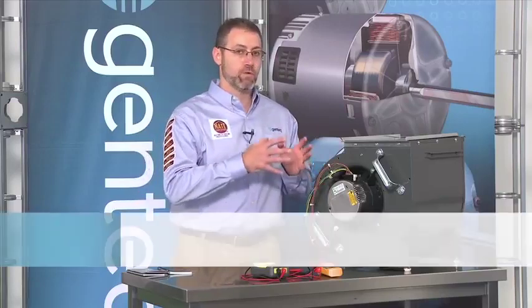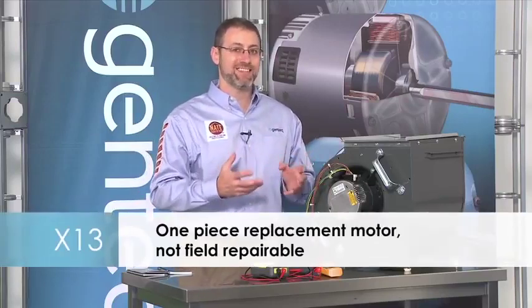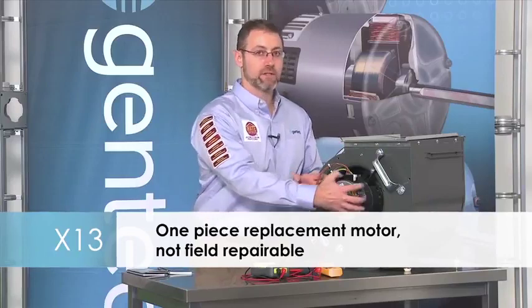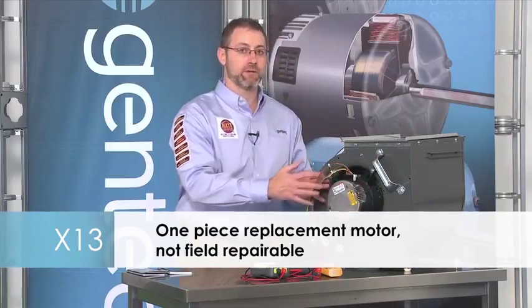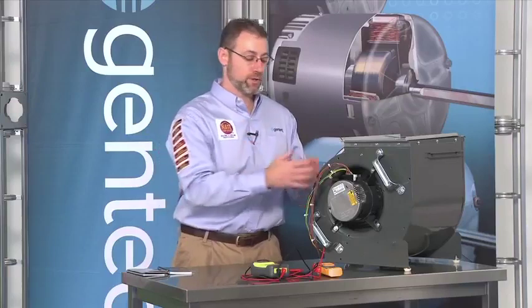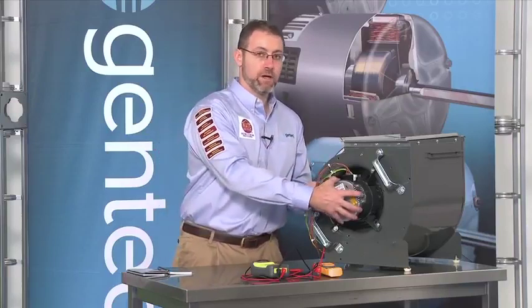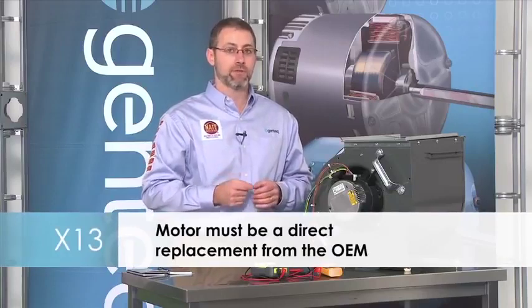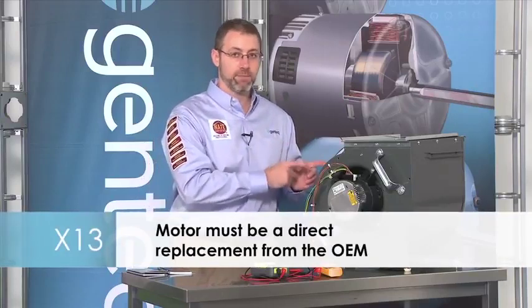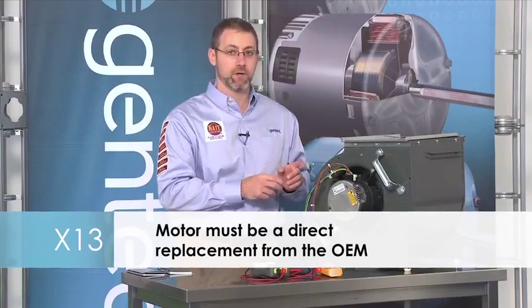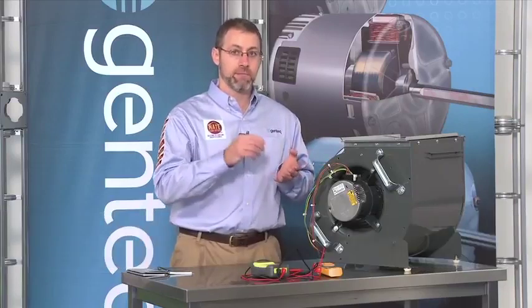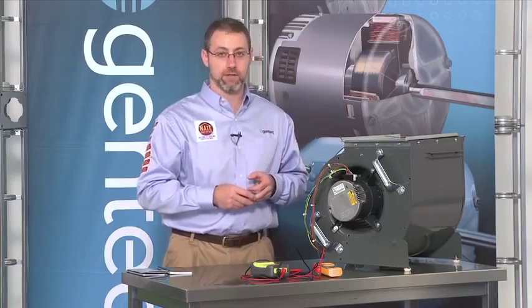If the X13 motor needs to be replaced, keep in mind that the X13, unlike variable speed, is a one-piece motor. Even though it is an ECM motor, it does have a control inside this motor shell. The X13 can only be replaced as one part. So if the motor's failed, you will get one whole motor and control assembly from the manufacturer. And you will have to go to the manufacturer of that appliance and get the X13 motor that goes not only in that manufacturer, but that model and that size system.